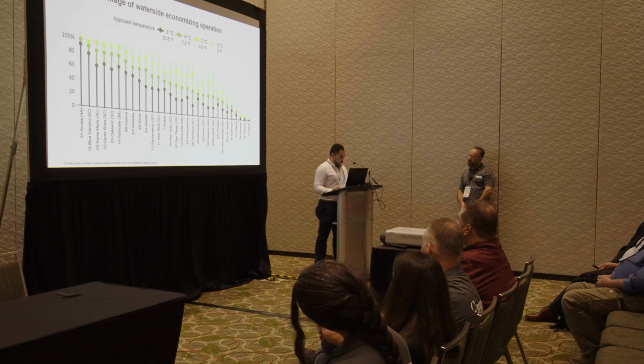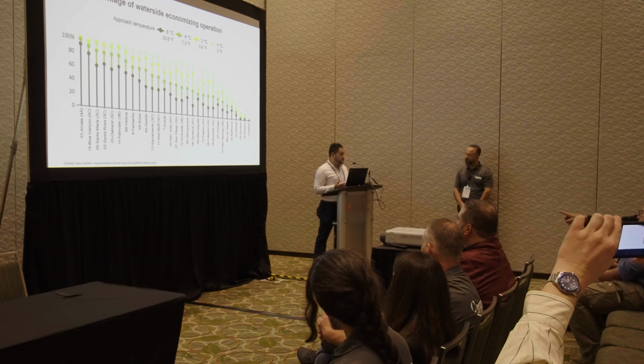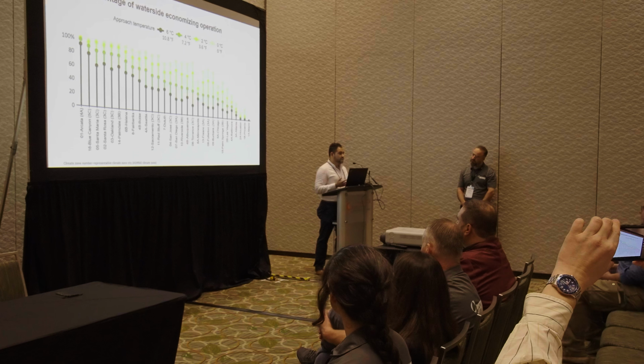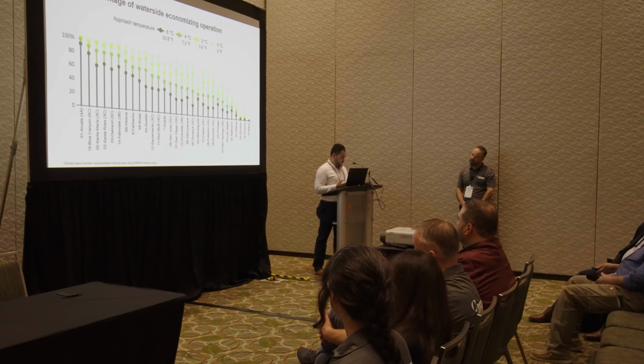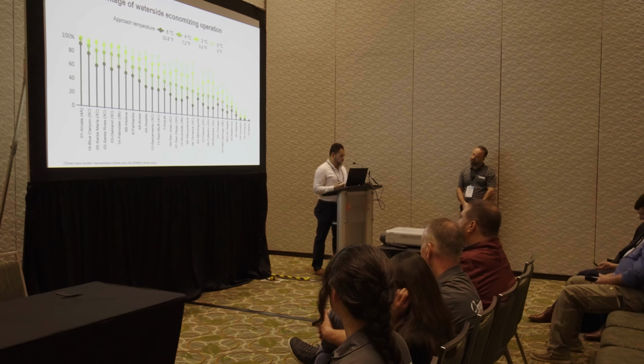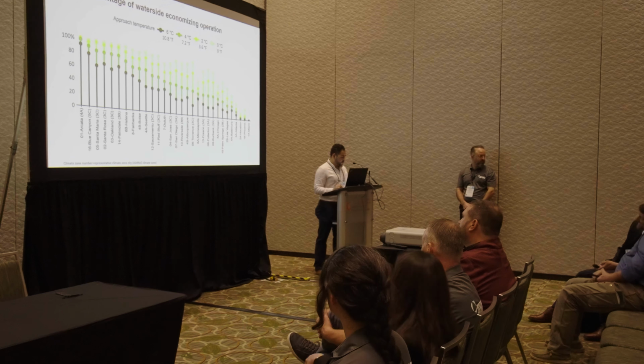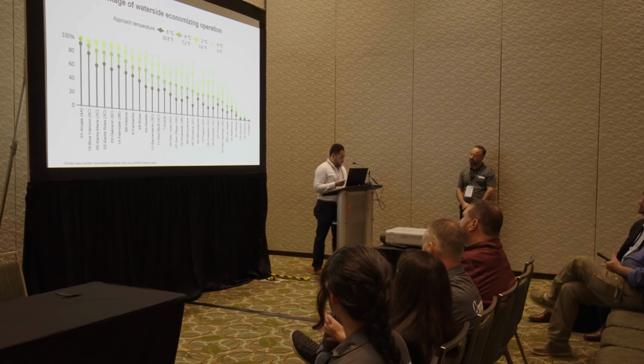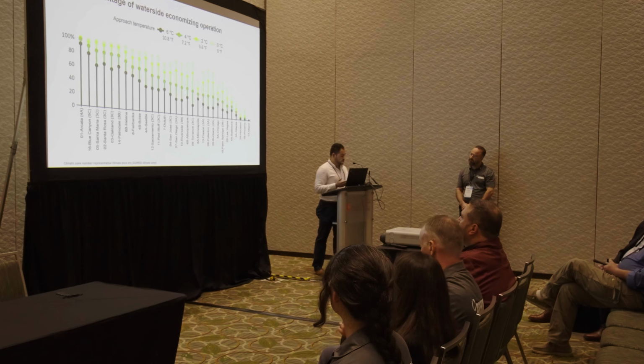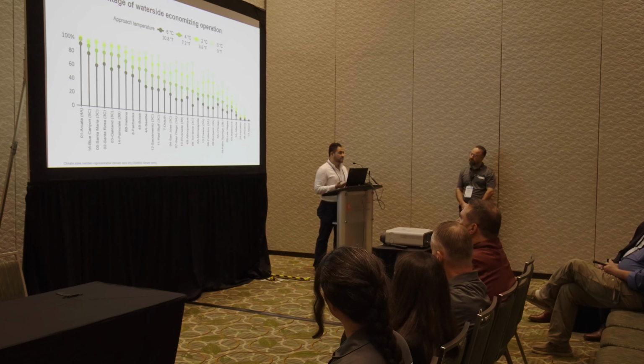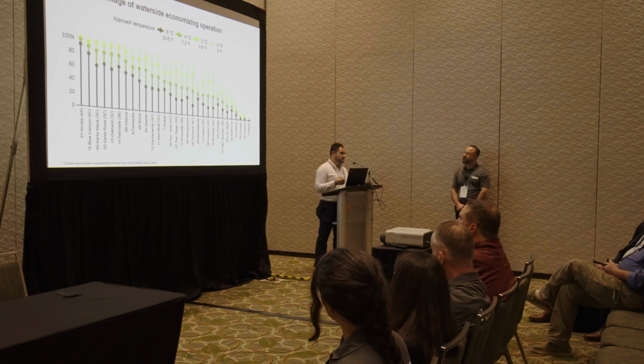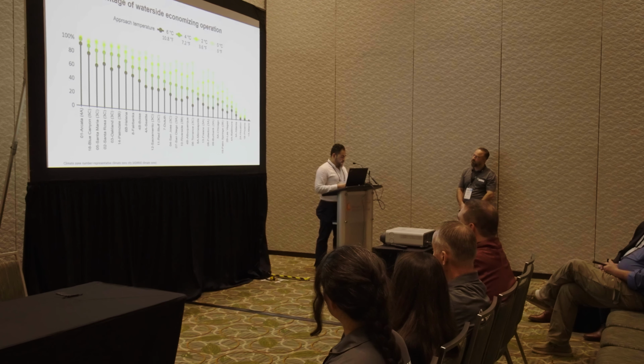For example, in California climate zone number 3, which is Oakland as a representative city, we saw that 50% of the models can supply the design chilled water temperature 60% of the time with an approach temperature of 11 degrees Fahrenheit. And the approach temperature is just a proxy of how well the cooling tower is performing.